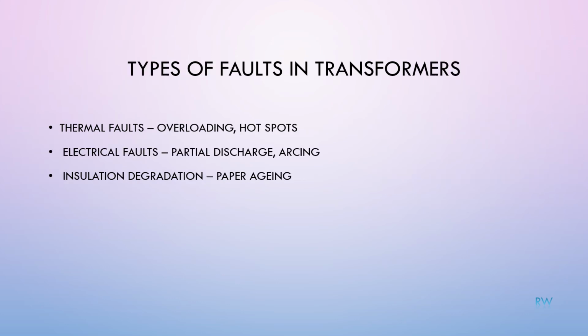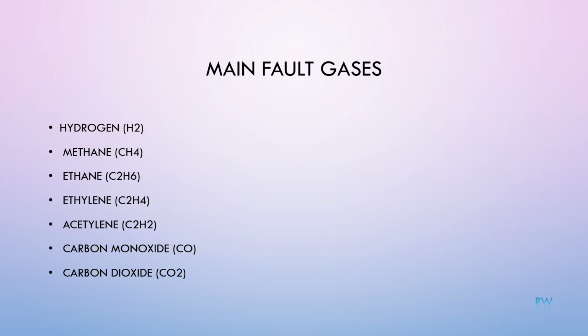Transformer faults are broadly classified into three categories: thermal faults, caused by overheating or overloading; electrical faults, such as partial discharge or arcing; and insulation degradation, mainly involving paper aging. Each type of fault generates specific gases. The key gases monitored in DGA are hydrogen, methane, ethane, ethylene, acetylene, carbon monoxide, and carbon dioxide. Each gas gives valuable information about internal transformer condition.